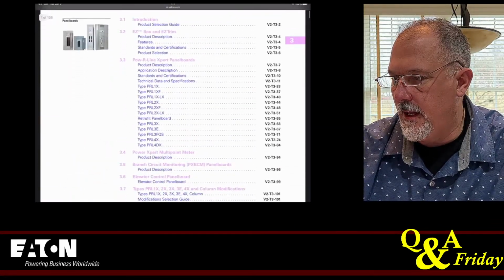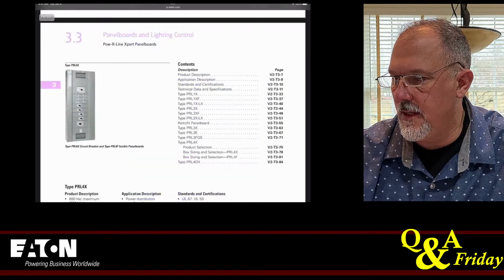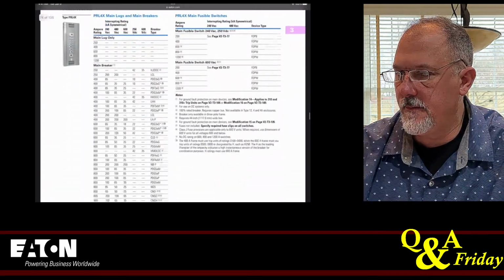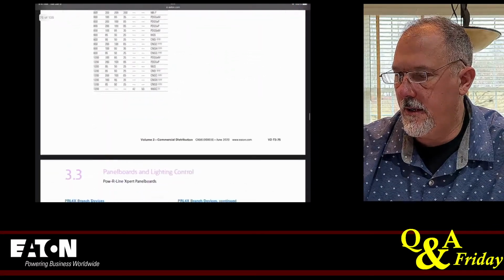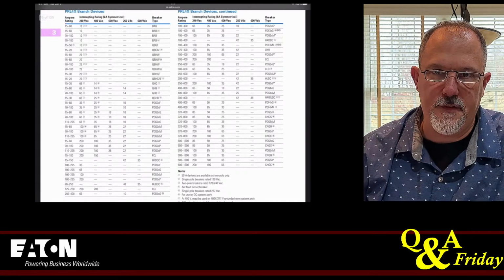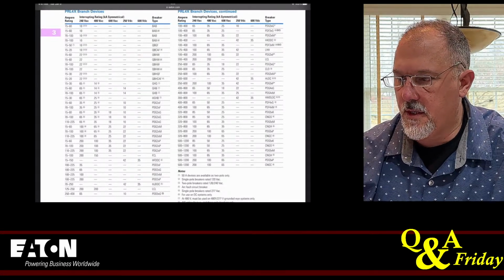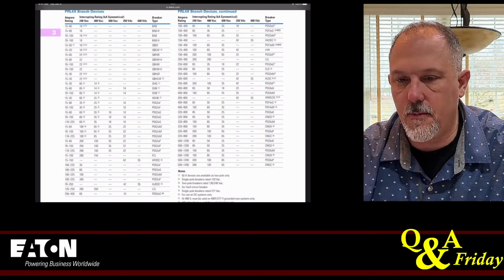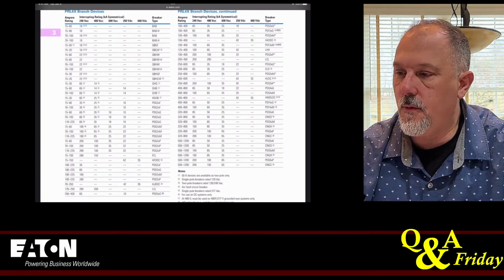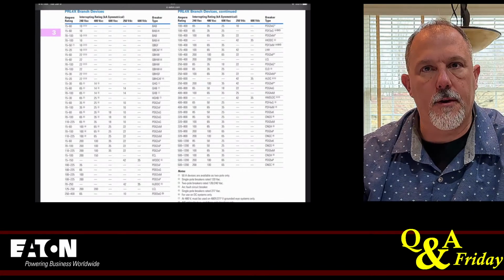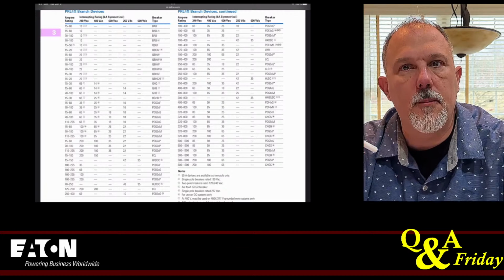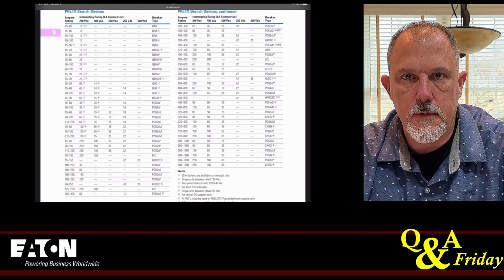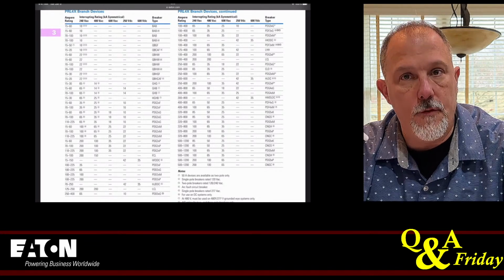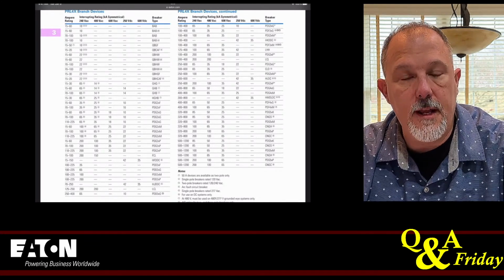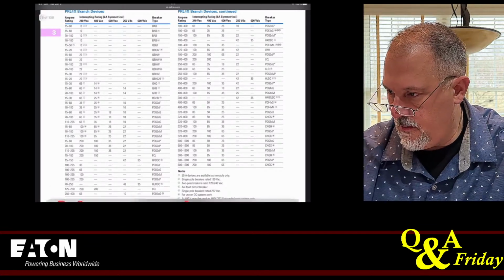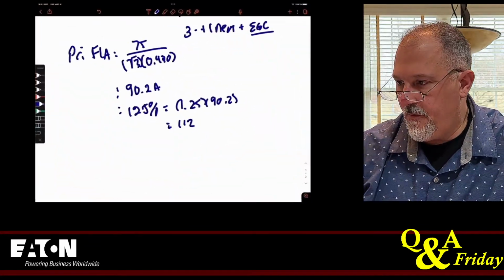So I'm going to click the very top. Now let's go to a Pow-R-Line 4X. There's your main breakers. And look at the options that you have with regard to any of the branches. So that Pow-R-Line 4X is going to be the cure-all for everything. So my recommendation would be to pick the panel, pick the equipment that you're going to put up there, and then make sure that the overcurrent protective device that you pick will fit in that panel.